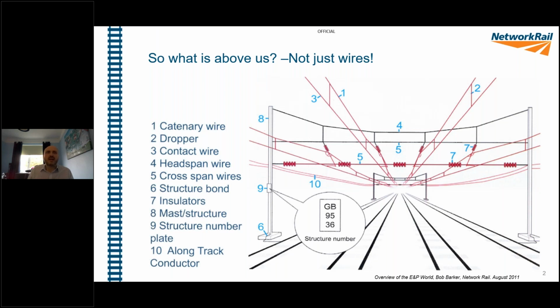You can see also that we have a structure number plate on there. It's really important from a safety point of view that we know these overhead line structures have unique identifiers, and if there is a problem or a fault, we need to be able to get to the structure. We know where it is, or if we're taking an isolation, we need to know where the isolation starts and ends, and where it's safe to work and where it's not safe to work. So structure numbers are a really, really important piece of safety information, as well as a piece of asset management information.